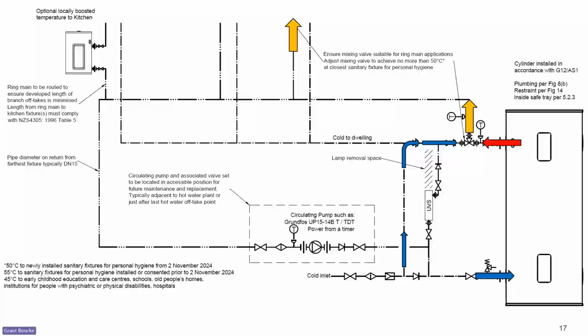But again, this illustrates why we want to make sure we've got that virgin cold water coming from upstream of the non-return valve, so that the mixing valve, when this happens, is getting a nice steady temperature cold water. It's not fluctuating as a little bit of hot mixes in with it. So that's what happens on that warm water system when a tap opens. I hope if you never quite understood this, or you're seeing it for the first time, that explains it and you can understand it okay.